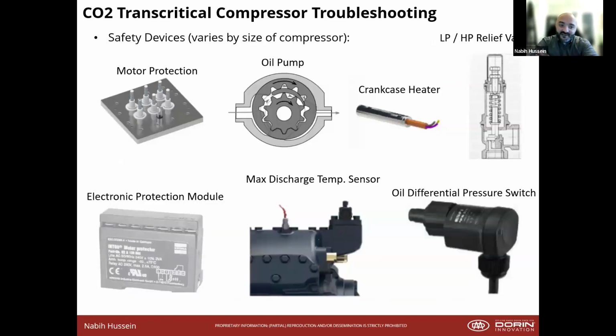But the protection devices on it is motor protection. Right here, you can see these two little prongs going up. That's a sensor that connects directly into the motor. And when that trips, it means your motor is overheating, so it turns off your compressor to protect the motor. An oil pump, it's a gear-driven oil pump. It's going to be pushing oil into your compressor. It is used along with the oil differential pressure switch. Once it senses a low differential pressure, you know that you have lack of oil, lack of lubrication. It would shut off your compressor.